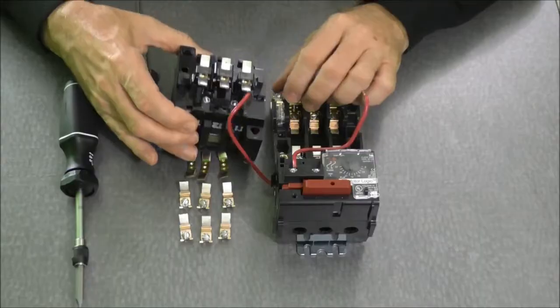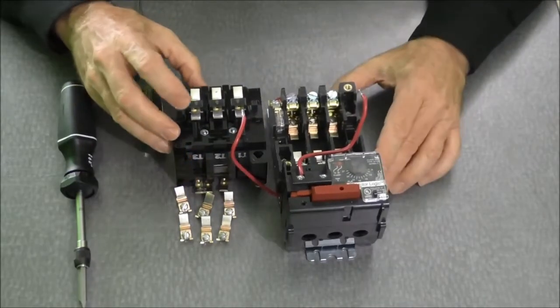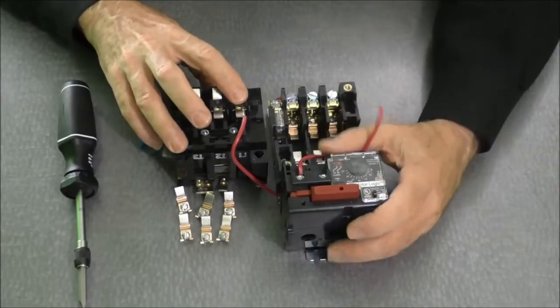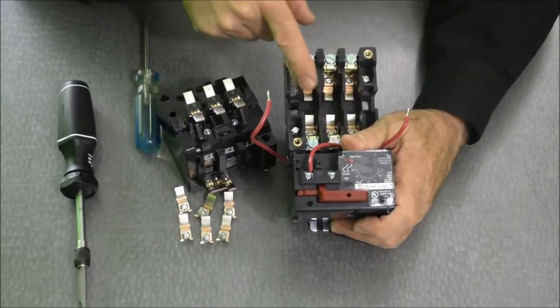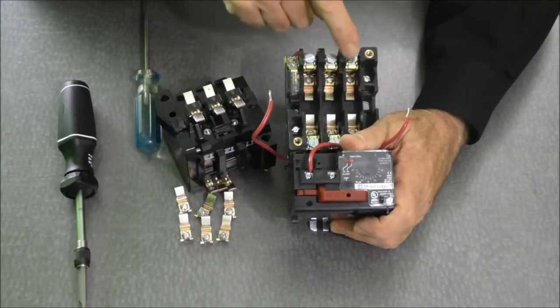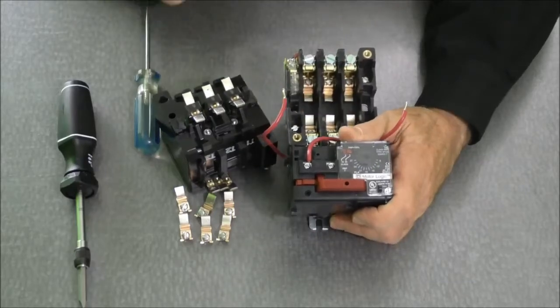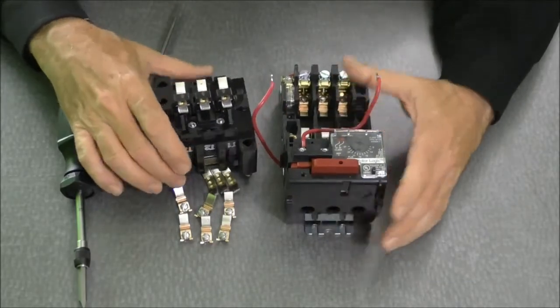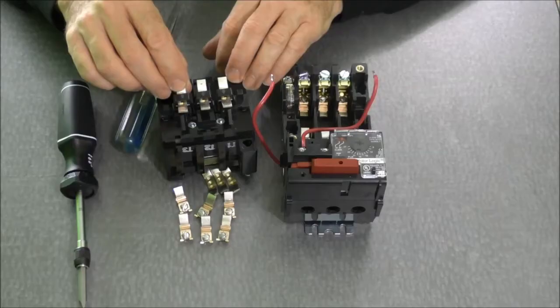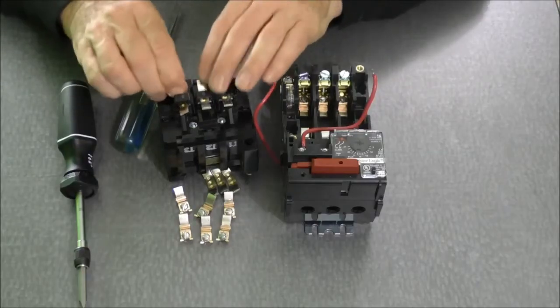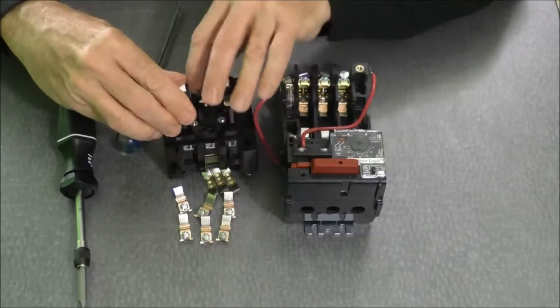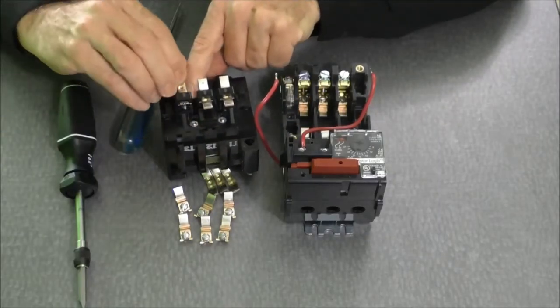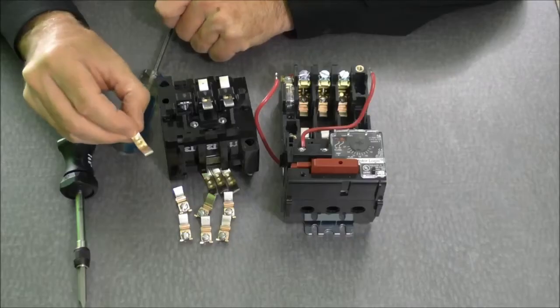So right here I have my six movable contacts and in the bottom of the contactor itself we have six stationary contacts. So we'll begin to remove those by taking off the terminal and bringing off the contact.